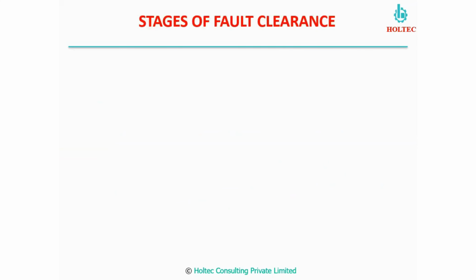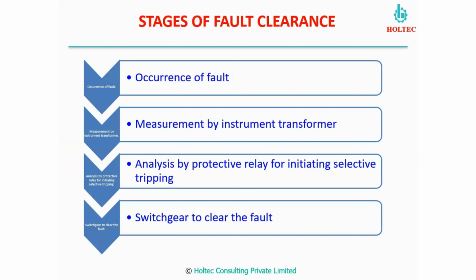Now let us discuss the stages of the fault clearances. When any fault has occurred, what stages are there in the fault clearing? So the first is the occurrence of the fault. Then we have measuring instruments through which we do continuous online measurement of the operating parameters. And whenever the fault occurs, this will give the reflections in the instrument transformers, and those will be analyzed by protective relays and initiate selective tripping. Okay, here the word selective is very important.